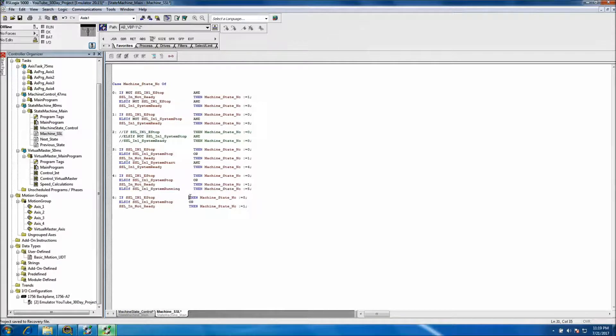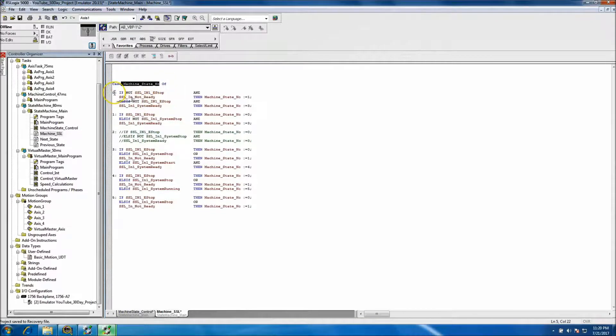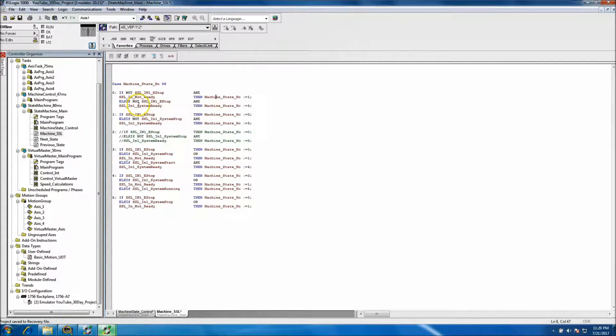Nobody's coming behind this simulation, but in real life you would want to do that. Let's look at this: in CASE of machine state — if it's in State 0 and there's no e-stop and the system is not in a not-ready state, then it can go to State 1.